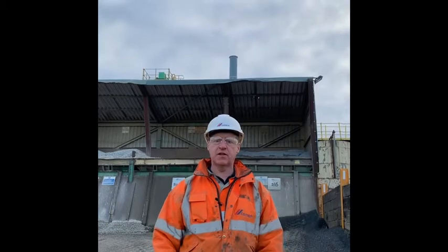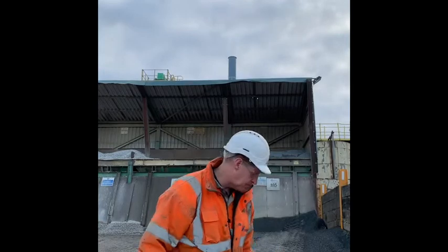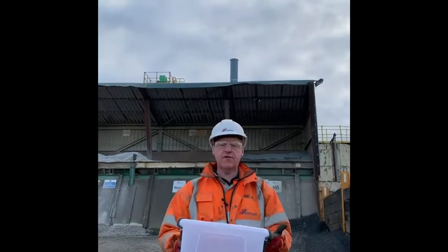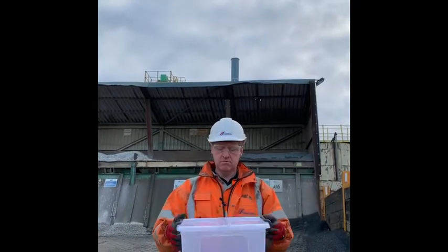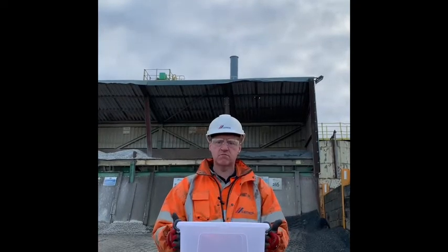It will tell you things like velocity of your stack, and how many milligrams of filler or particulates were emitted during the stack test. From this, you can work out how much filler or particulates were emitted from your stack in a working day. My maximum permitted is 50 milligrams, and if I were to emit it at my stated velocity, how much filler do you think would go up my stack? Small amount? Large amount? I'll show you. At 50 milligrams, it would be enough filler to fill this plastic box. Quite a lot, isn't it?